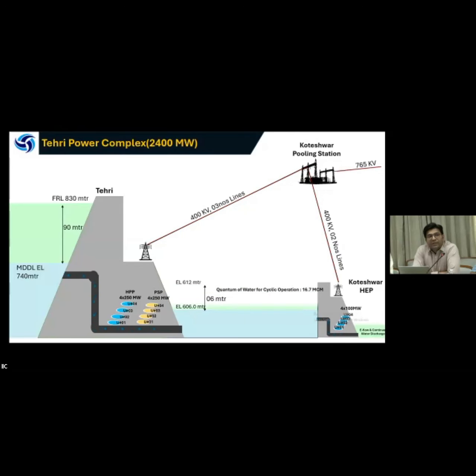The Tehri HPP and Tehri PSP are co-located and share common infrastructure such as the dam, lower reservoir, upper reservoir, and the transmission system for power evacuation. The 400 kV GIS is common to both projects and is connected by 3 numbers of 400 kV transmission lines to the Koteshwar pooling station, developed by the Power Grid Corporation of India. Further, this 400 kV is stepped up to 765 kV and connected to the Meerut substation.